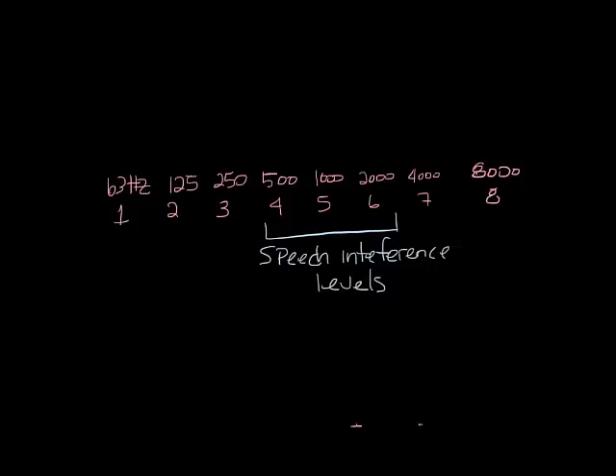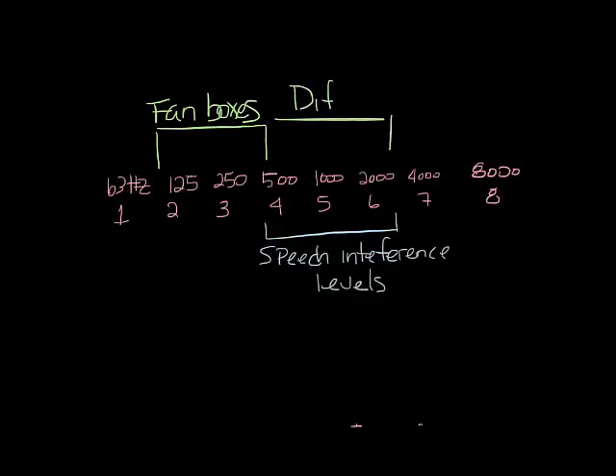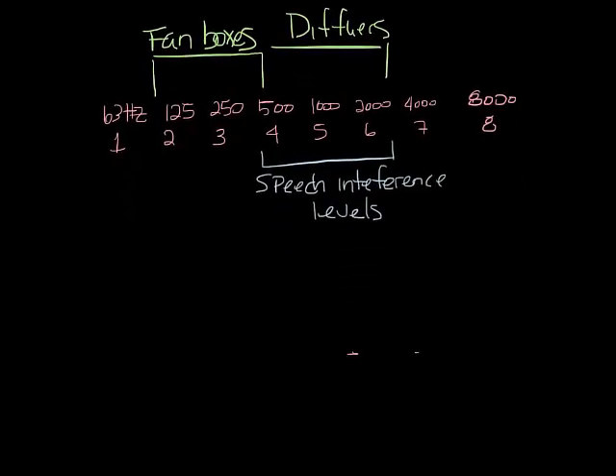Different products generate their highest sound levels in different octave bands. Fan boxes, for instance, have their highest sound levels in the second and third band, while grills and diffusers create their highest sound level in the fourth, fifth, and sixth bands. You often see HVAC data shown in octave bands 2 through 7 only, because that's where the product's sound levels peak. But in room design, high decibels in the first and eighth octave bands can also cause problems.